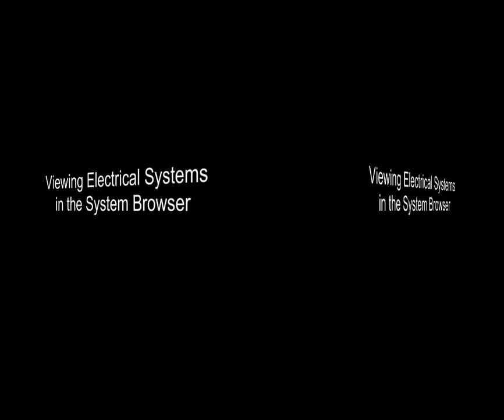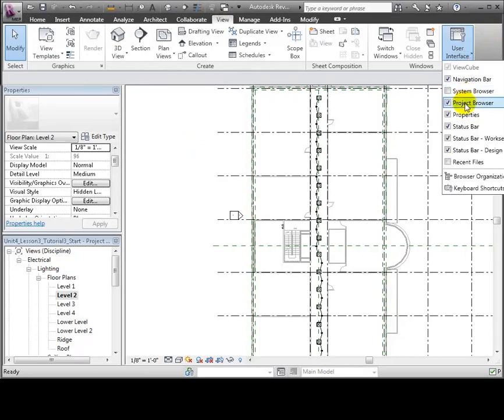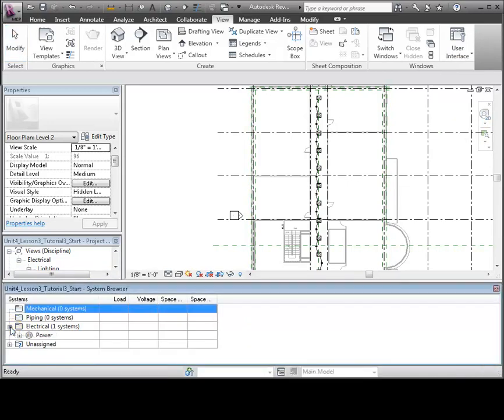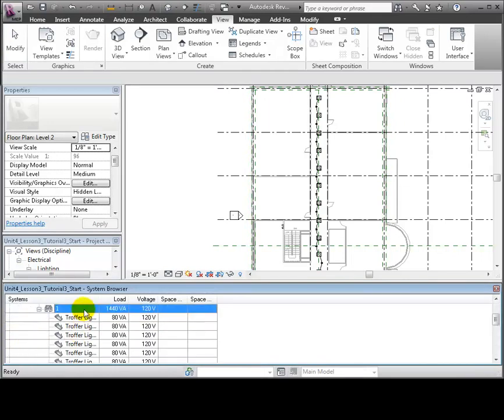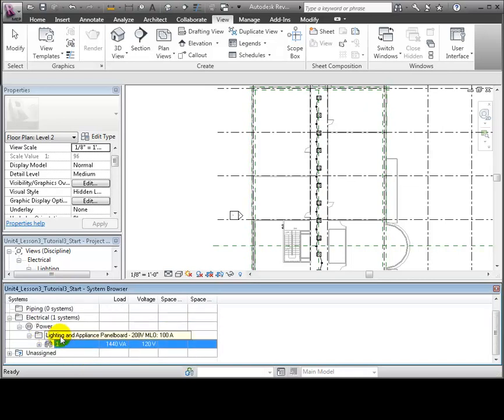You can review all of the power and switching systems defined in your project, and the elements associated with each system in Revit MEP's System Browser. Switch to the View tab, then open the User Interface drop-down to turn on the System Browser view, and it appears below the drawing area. The System Browser lists all the MEP systems. You can expand the Electrical, then Power section, and you'll see the Lighting and Appliance panel boards placed in the project, and the circuits assigned to each panel. Each circuit shows all of the fixtures assigned to that circuit, and the total load created by the fixtures in the circuit. This entry in the System Browser corresponds to the panel that we placed on Level 2, and the circuit for the corridor lighting fixtures.